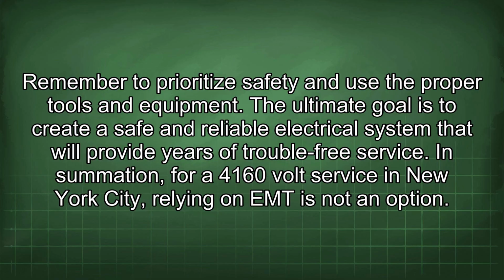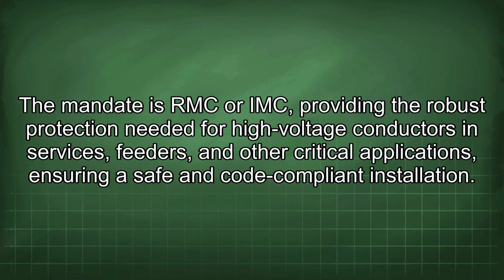In summation, for a 4,160-volt service in New York City, relying on EMT is not an option. The mandate is RMC or IMC, providing the robust protection needed for high-voltage conductors in services, feeders, and other critical applications, ensuring a safe and code-compliant installation.